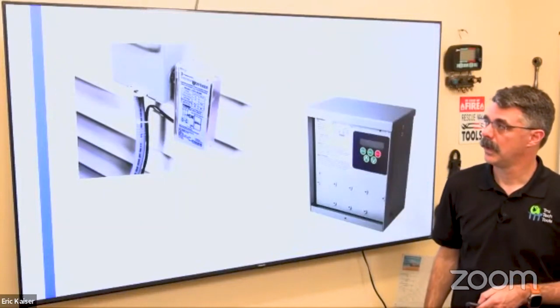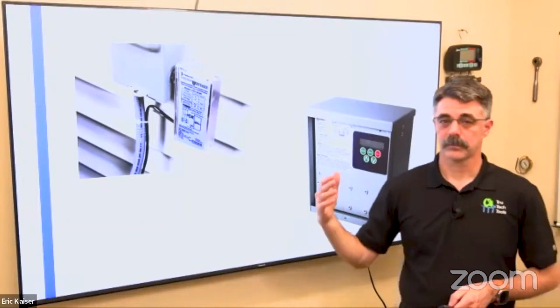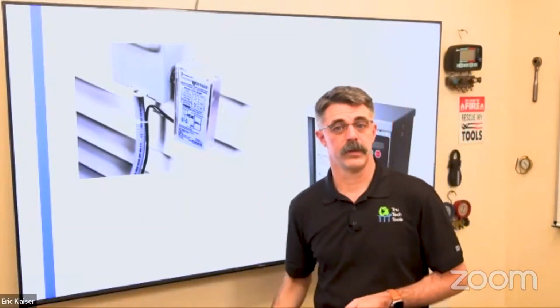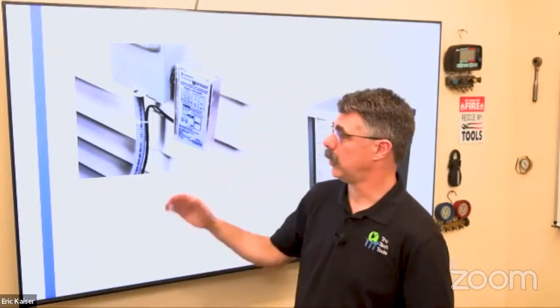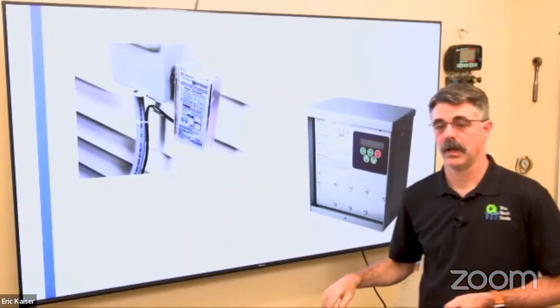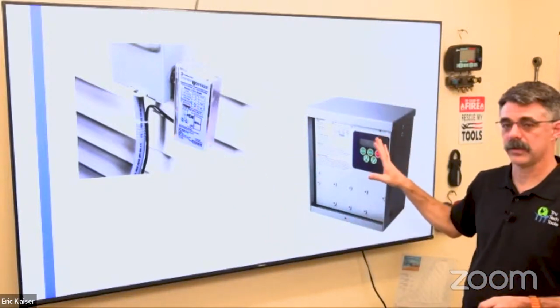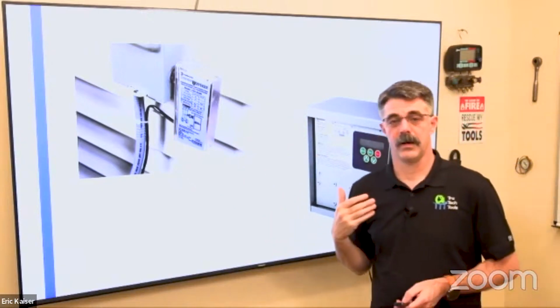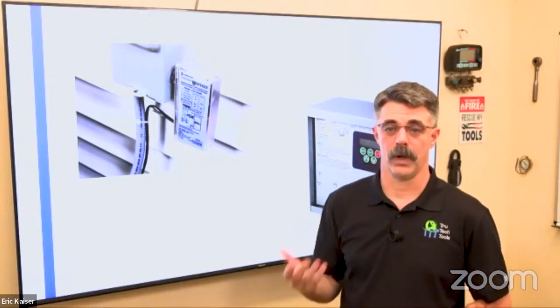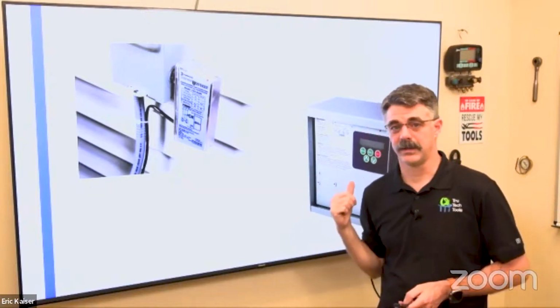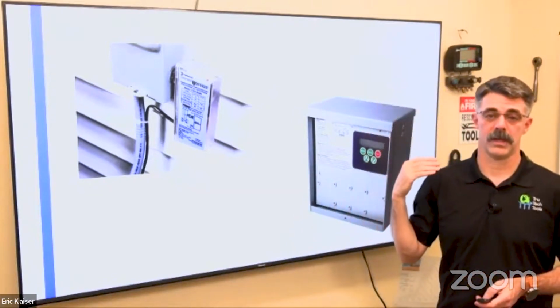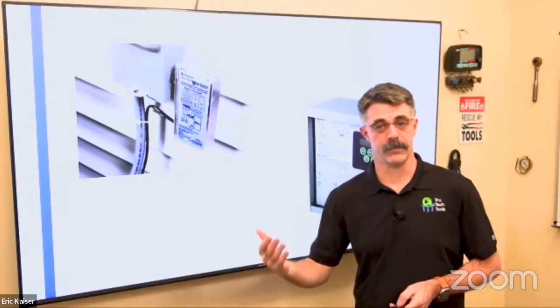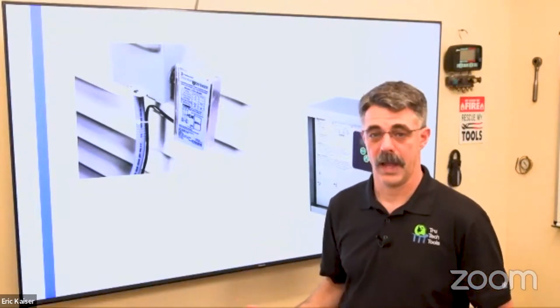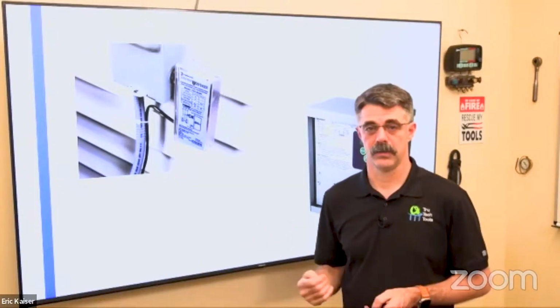Okay. Auxiliary devices. A lot of these units, especially if we're doing inverters, variable speed things, have electronics in there. It's important to protect those electronics. So something as simple as surge suppression, a device like this one, has a built-in voltage monitor on it, as well as surge suppression. It's got a contactor in there that turns the equipment off if it gets high voltage or low voltage. And it monitors for spikes and tells you what we get for spikes.